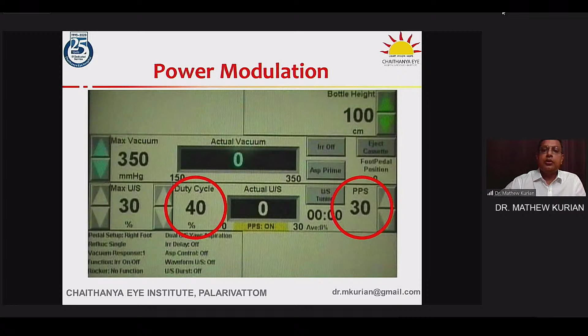So for example, if you have 2 pulses per second, you will have half time on, half time off, in 2 cycles. 30 pulses per second means that you have 30 on-off cycles going on during that time. The less amount of chatter and the more continuous form of emulsification happens in the higher pulse per second rates. So this interrupted power looks something like this.